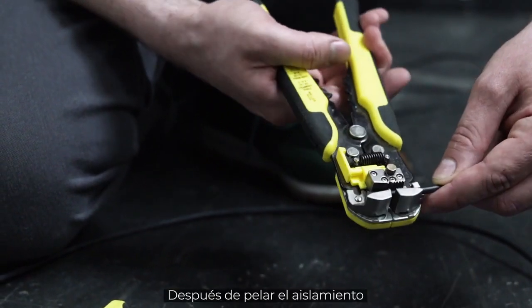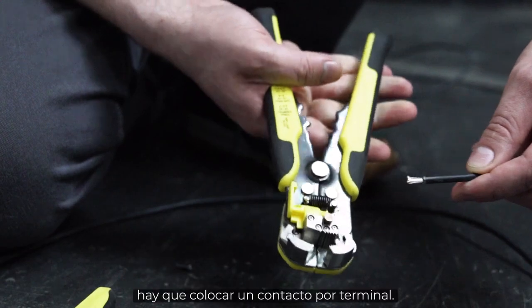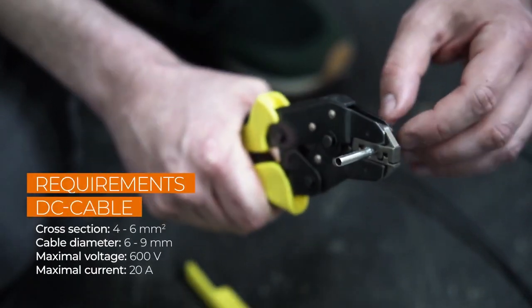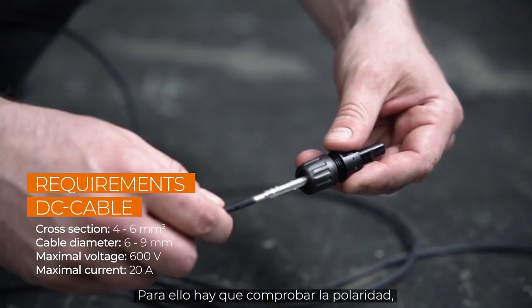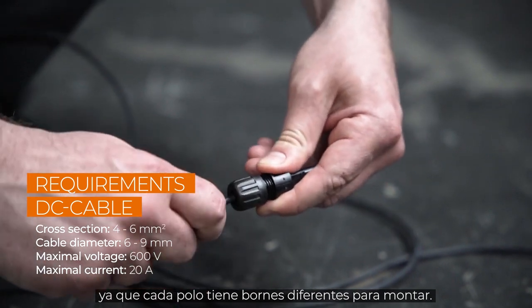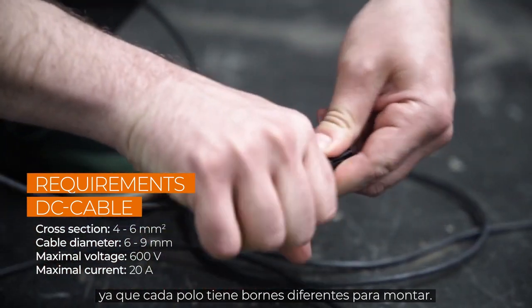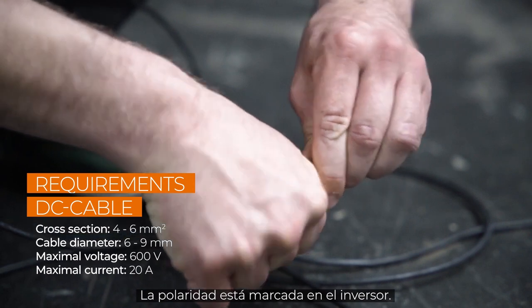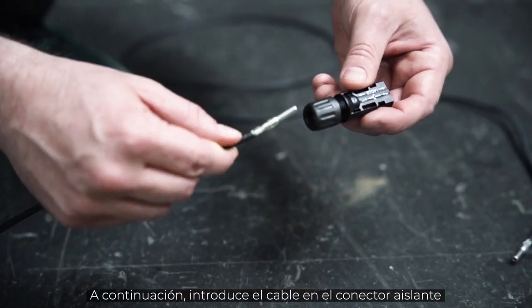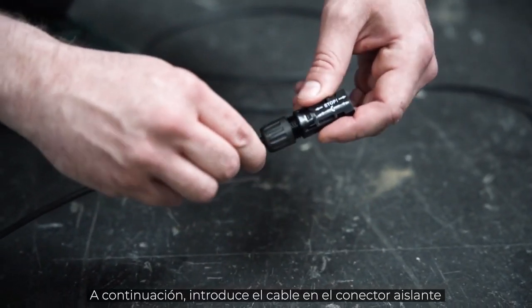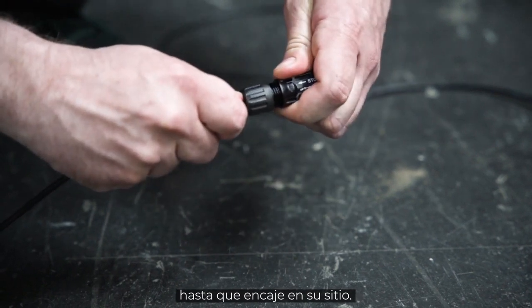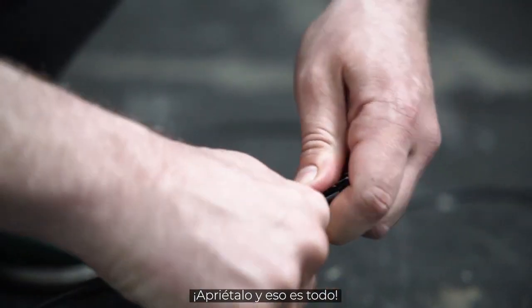Now let's take a look at the DC connector. After stripping the insulation, you have to attach a crimp contact. For this, you have to check the polarity, because each pole has different terminals that need to be crimped. The polarity is marked on the inverter. Then push the cable into the insulating sleeve until it snaps into place. Screw it, and that's it.